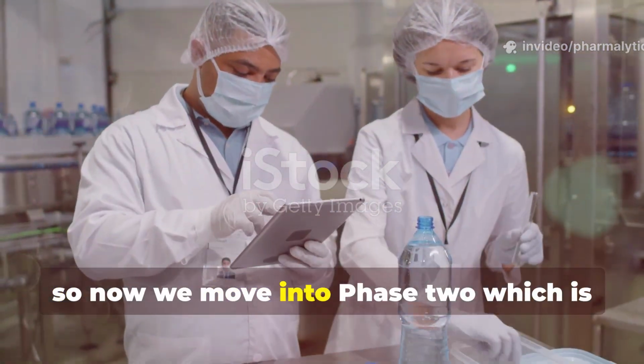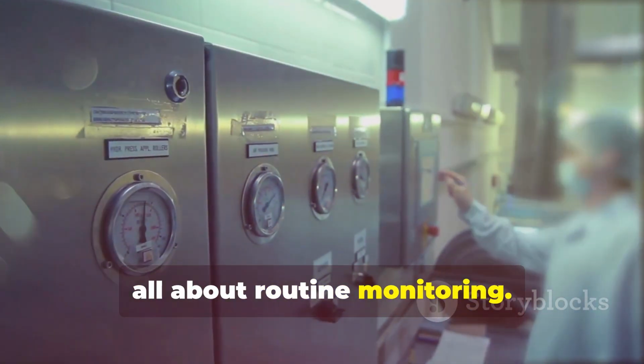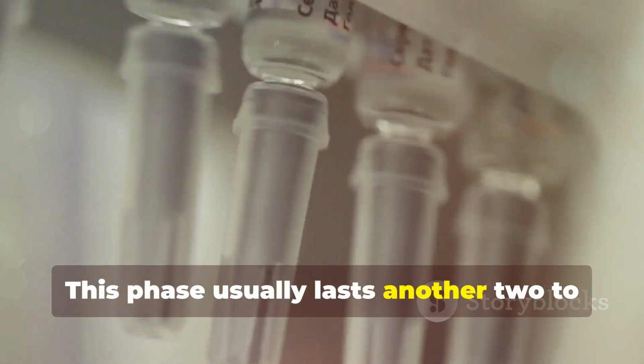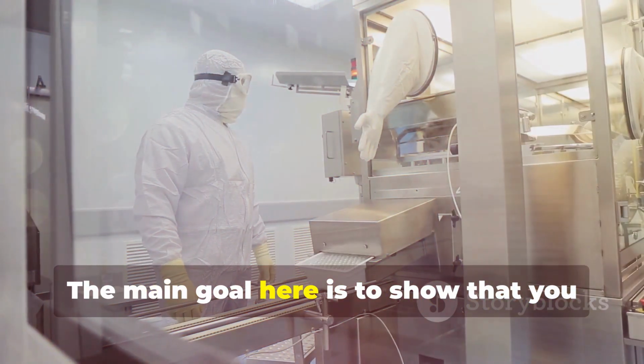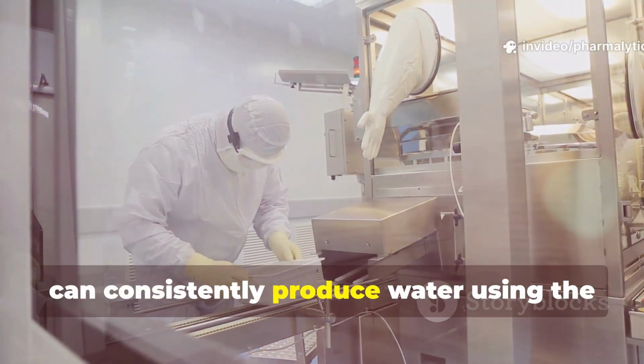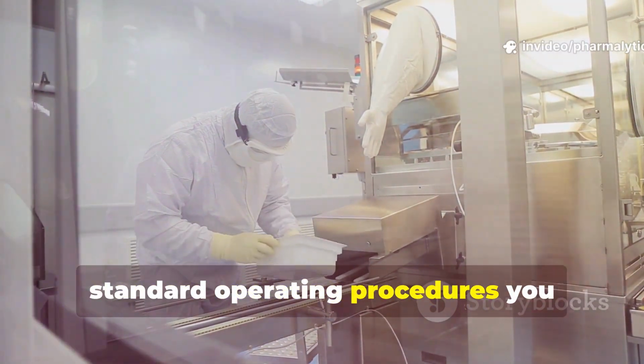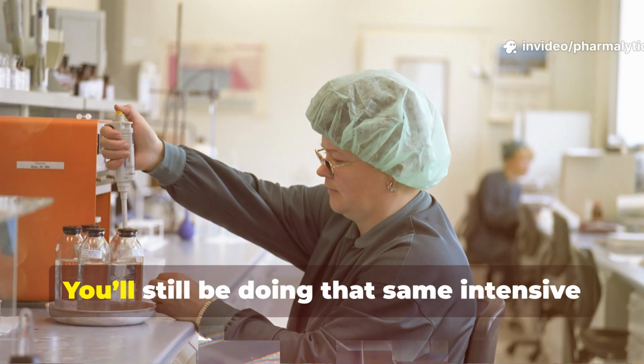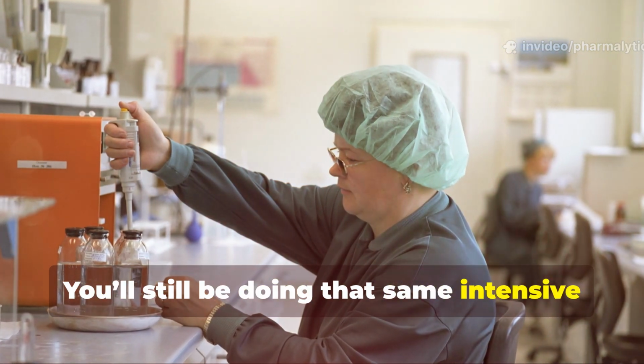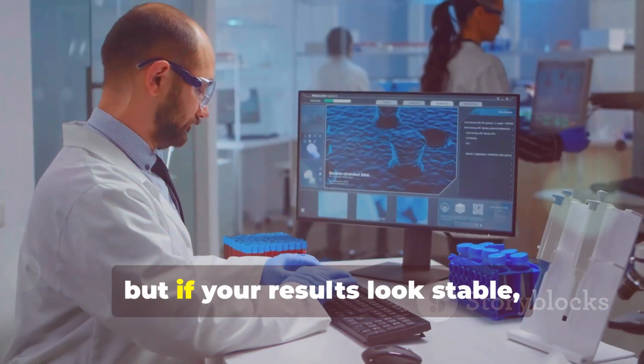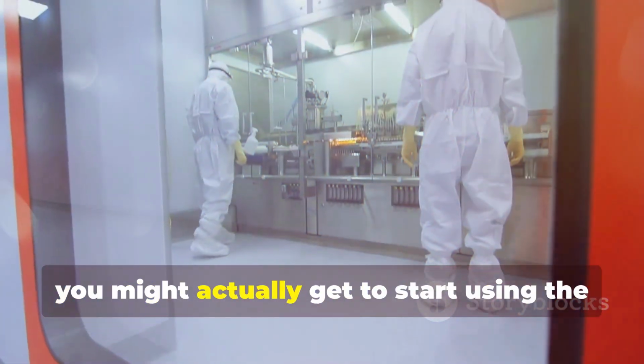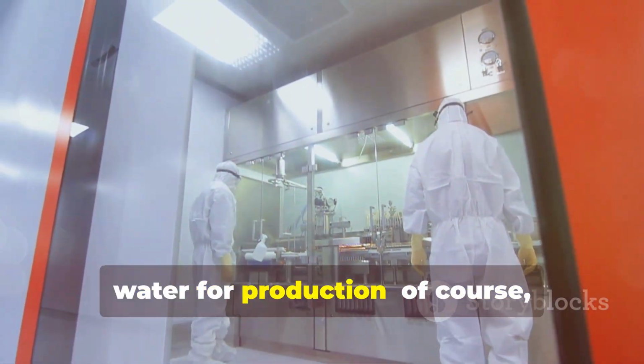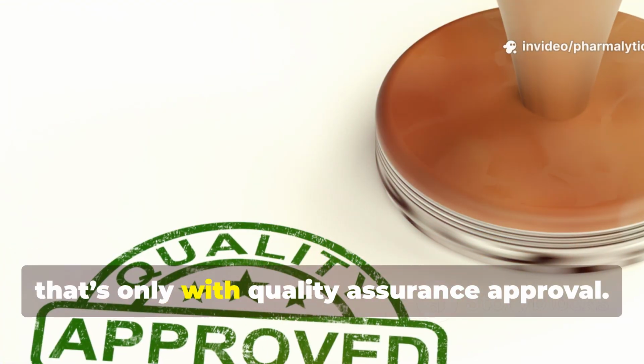Alright, so now we move into phase 2, which is all about routine monitoring. This phase usually lasts another 2 to 4 weeks. The main goal here is to show that you can consistently produce water using the standard operating procedures you developed in phase 1. You'll still be doing that same intensive daily sampling, but if your results look stable, you might actually get to start using the water for production. Of course, that's only with quality assurance approval.